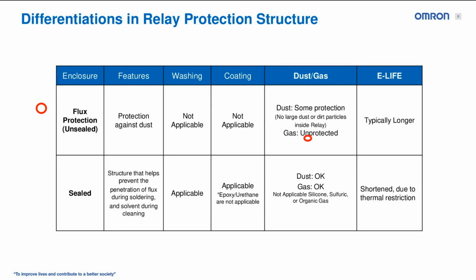Now, what's good about these relays, why it's good to look at unsealed, is if you need a longer electrical life, these relays will potentially have a longer electrical life than a sealed relay. And that's because you're allowing that hot air from inside the relay to escape through whatever break in the seal there is.